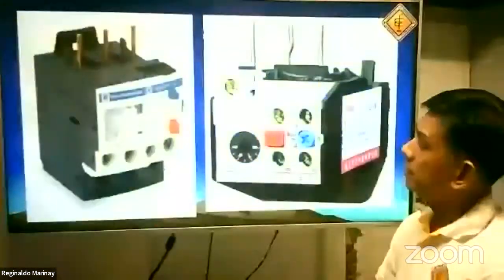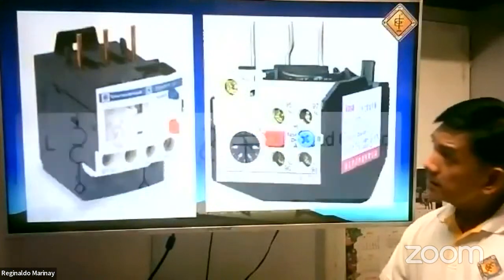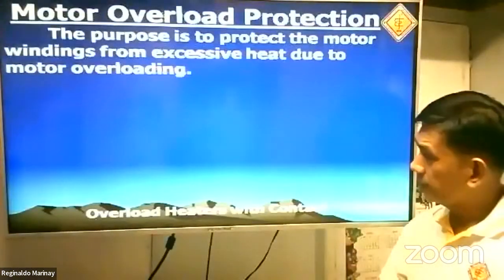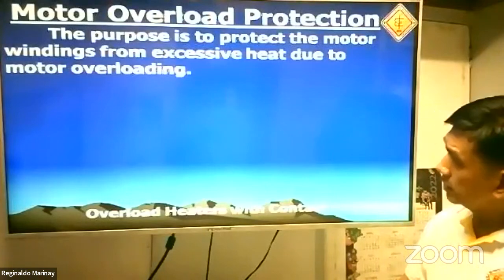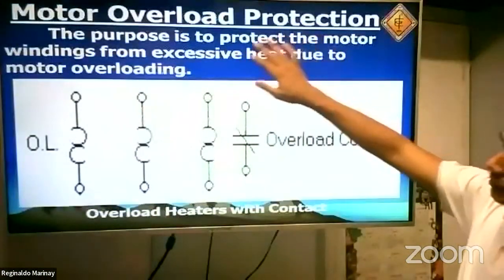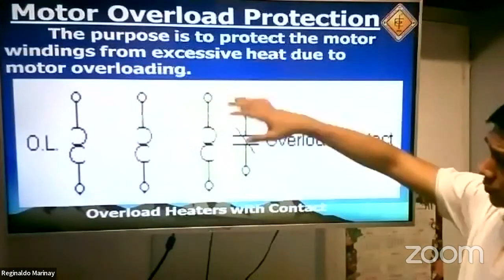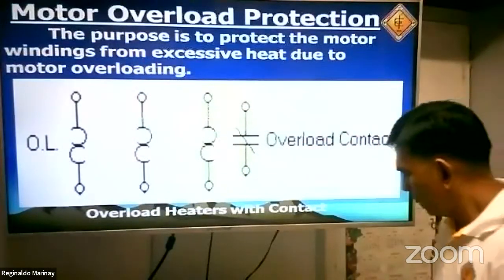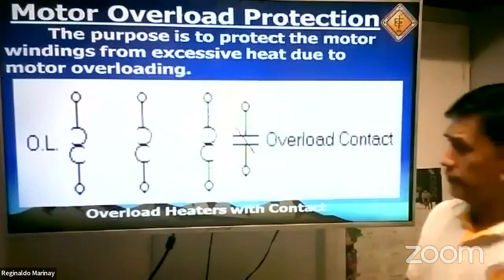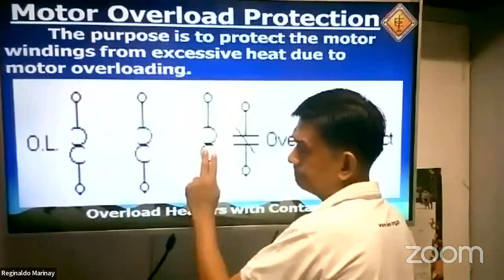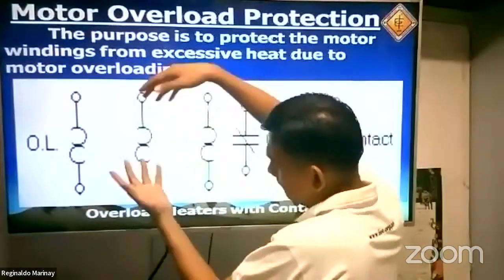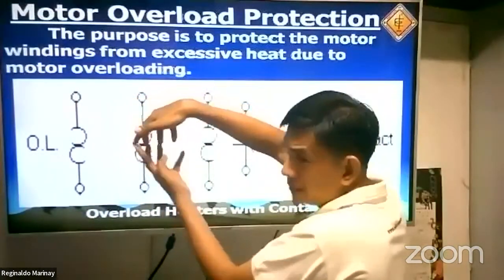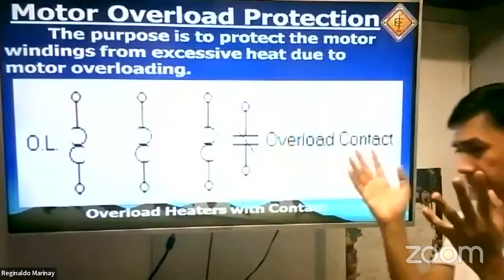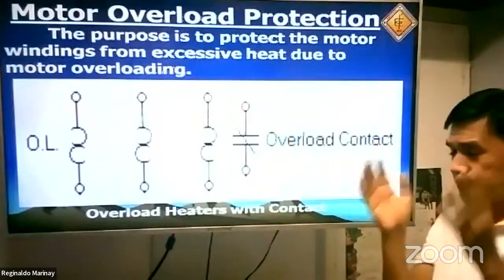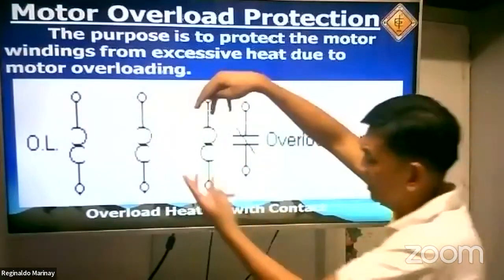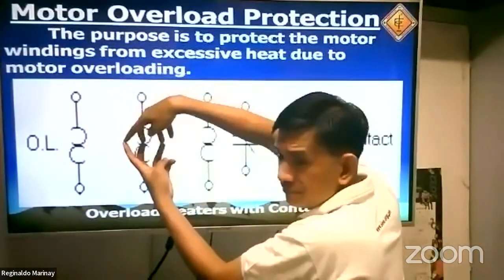Okay, we have the motor overload protection. This is an overload relay. Okay. Actually, I already gave you an idea about the overload relay. The purpose is to protect the motor windings from excessive heat due to motor overloading. When you overload a motor, this is normally closed, actually. This is going to the motor circuit. That is normally closed. If the motor becomes overloaded, let's say your motor is 100 ampere, but once the current flowing is more than 100 ampere, this will become open.